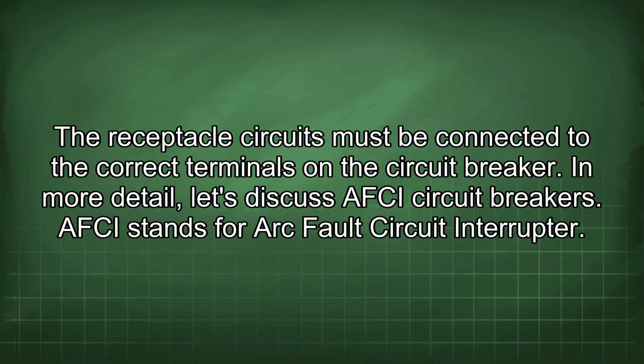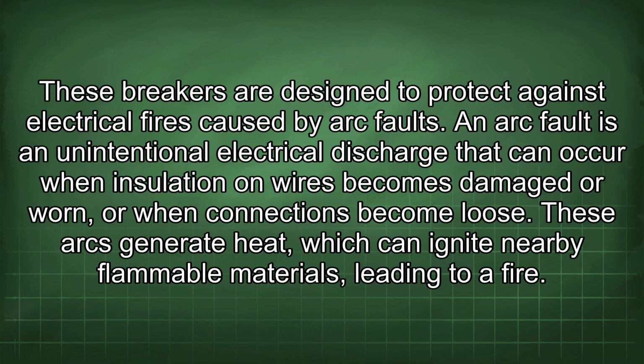In more detail, let's discuss AFCI circuit breakers. AFCI stands for Arc Fault Circuit Interrupter. These breakers are designed to protect against electrical fires caused by arc faults. An arc fault is an unintentional electrical discharge that can occur when insulation on wires becomes damaged or worn, or when connections become loose. These arcs generate heat, which can ignite nearby flammable materials, leading to a fire.